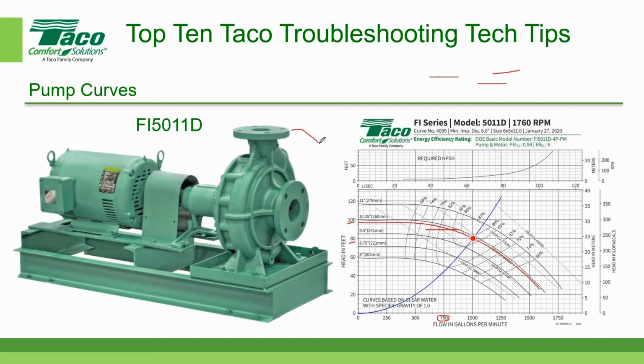And here's one of the things that we have to make sure we do properly here. Okay, so the pressure differential, the delta P across the pump, that's from the suction to the discharge. But to get the true delta P, we have to make a correction for the pump size, because the inlet on an end suction pump is generally larger than the outlet.